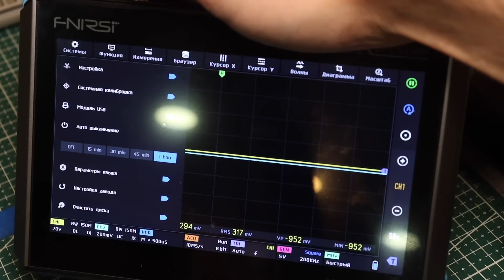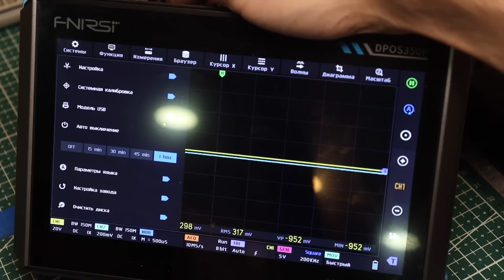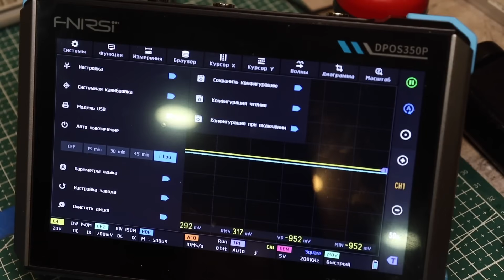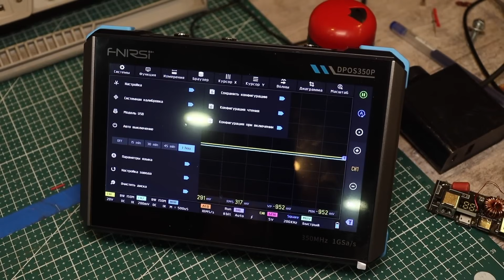Next are the system settings. Here we can clear the device memory, select the preferred language, reset everything to factory settings, set the automatic power off time or disable this function entirely, perform a system calibration, and remember, system calibration must always be done before putting the device into operation. And then there are the save settings. That covers the main settings of this device. Now let's take a closer look at its functionality.